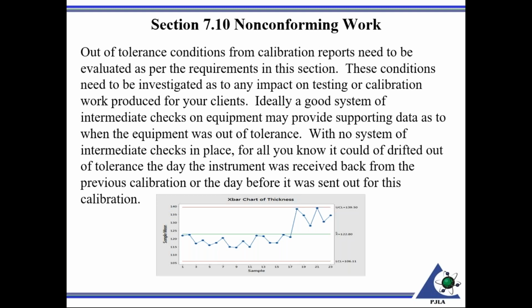So basically, you'll see you have to do an impact analysis on any testing or calibration produced for your clients that were incorporated with those as found failures. Ideally, I'm going to get a little bit off subject here. Intermediate checks for equipment may provide supporting data as to when the equipment was out of tolerance.